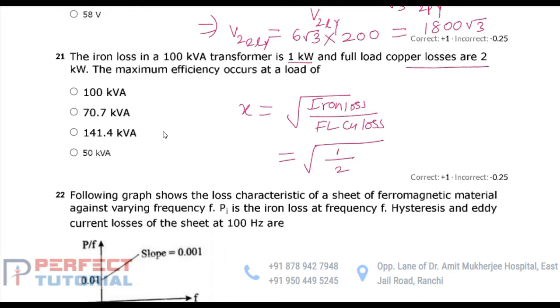Now see, load kVA at x of load is equal to what? x times the full load kVA. Full load kVA rating of transformer is 100 kVA. So simply you multiply full load kVA 100 by the fraction of loading at which maximum efficiency occurs. So x times full load kVA, that is equal to 1 by root 2 multiplied by 100 to give 70.7 kVA. Now you see next problem.